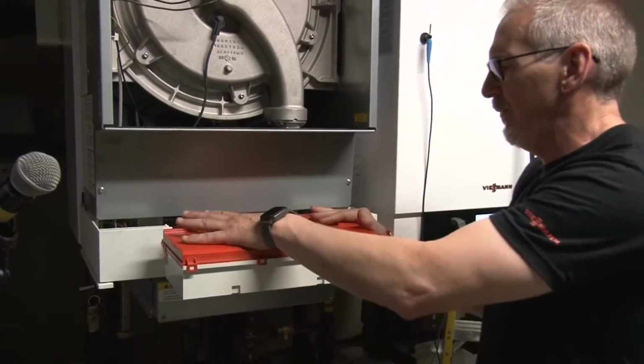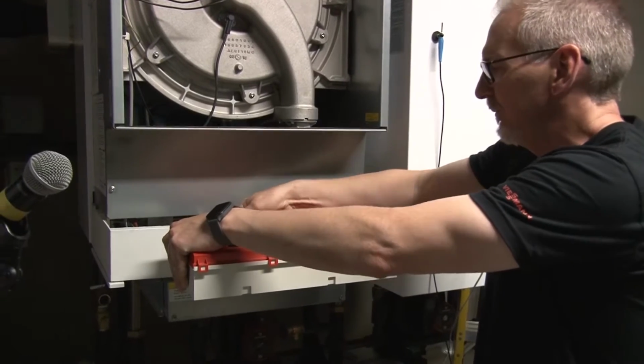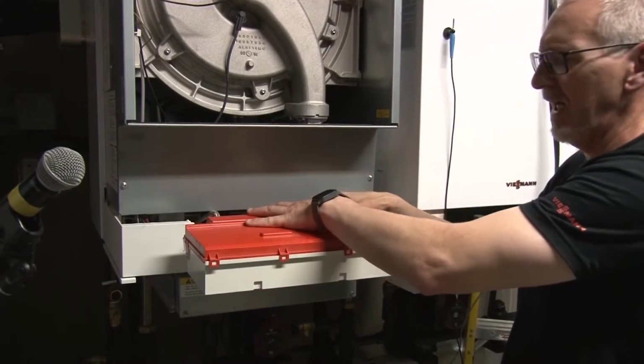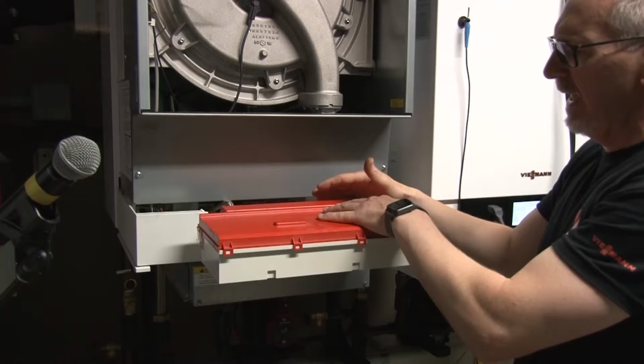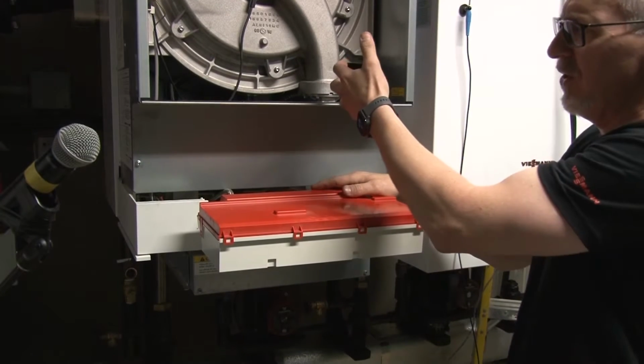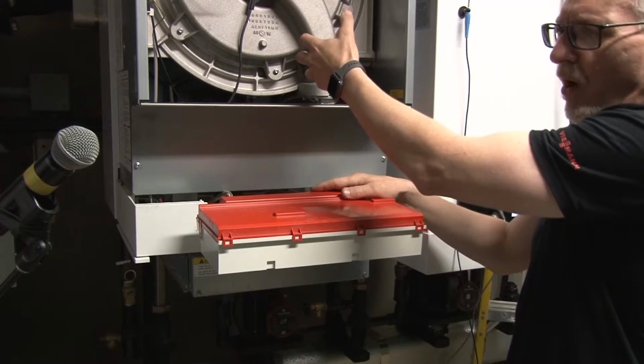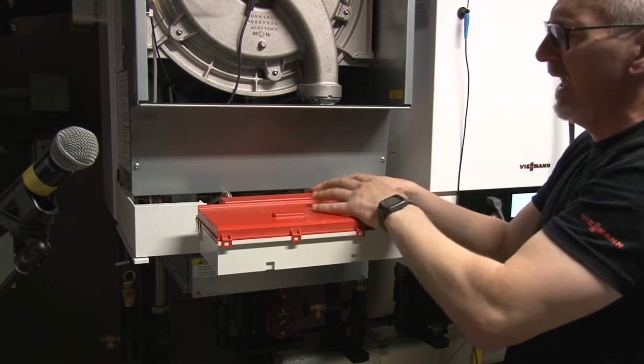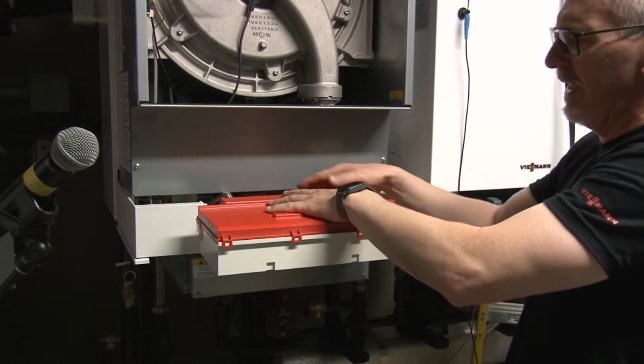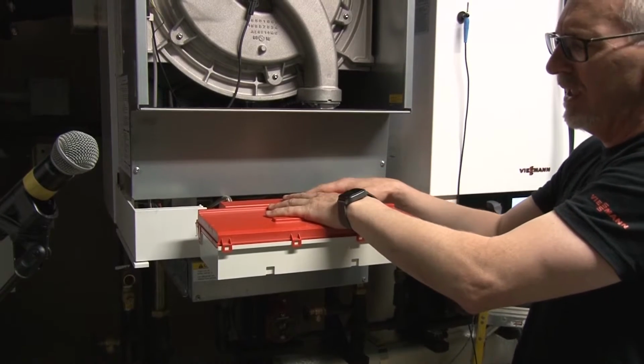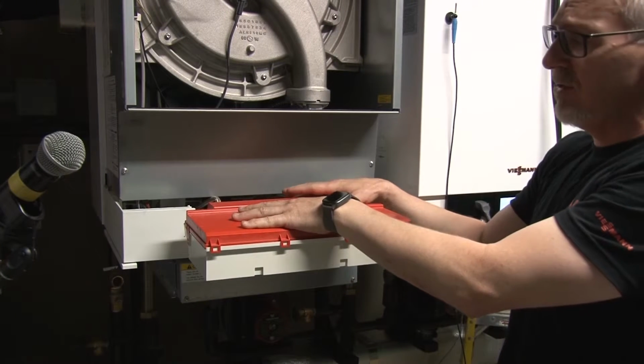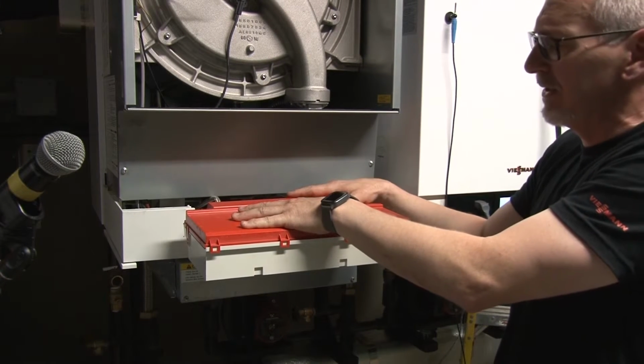down. When we're doing service, it's important to keep this little cover on the control. If I pull this cover off, there's live voltage back here. And of course, if I'm doing service, I'm going to be adding water or washing this heat exchanger, and if water gets on this control and it gets exposed to that line voltage, you let the smoke out of the control, as they say, and you can't put the smoke back in. That's going to be a new control.